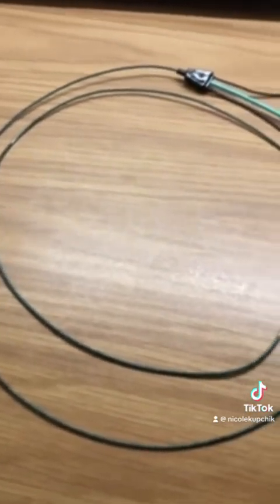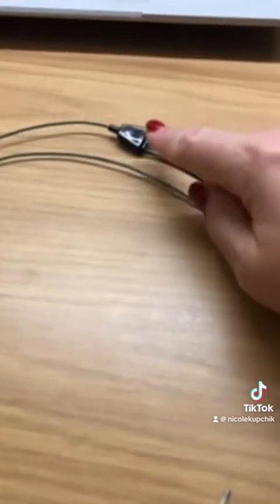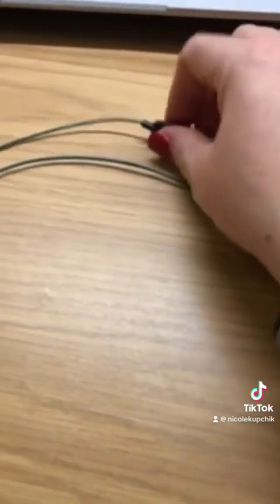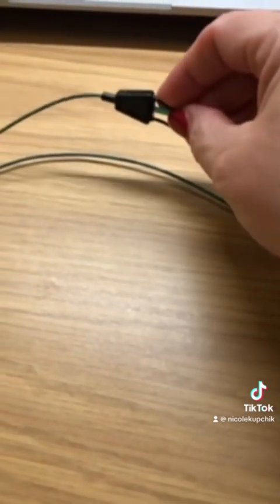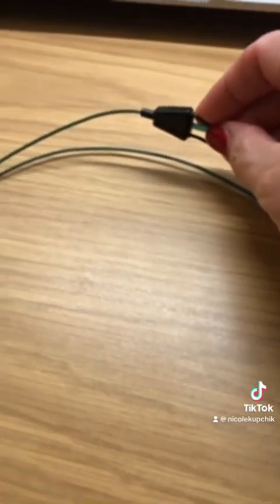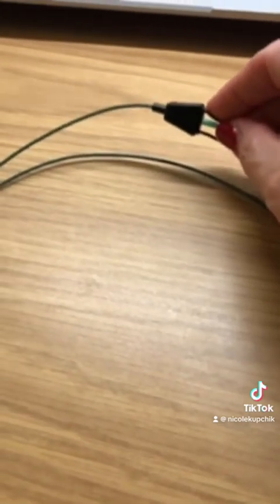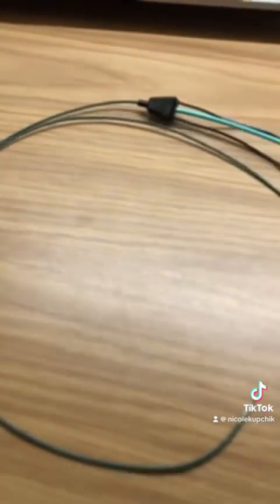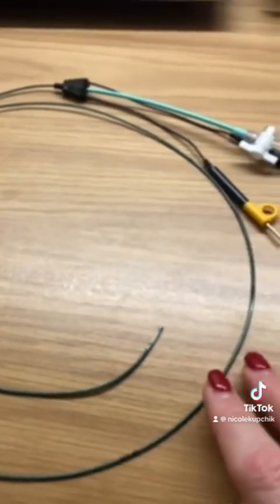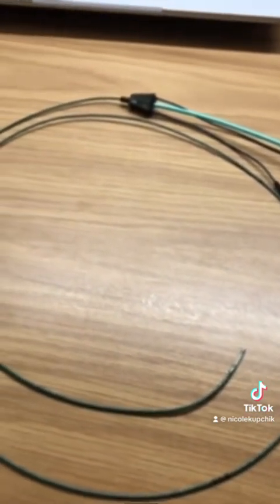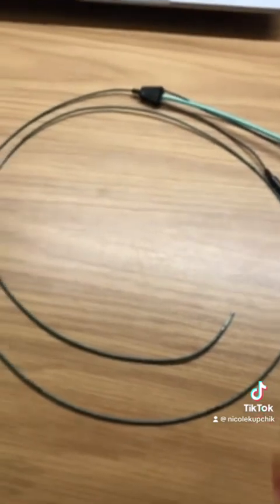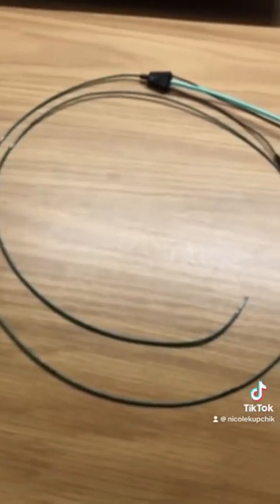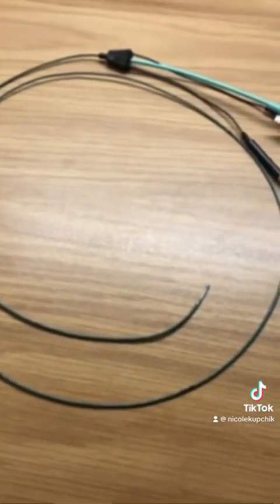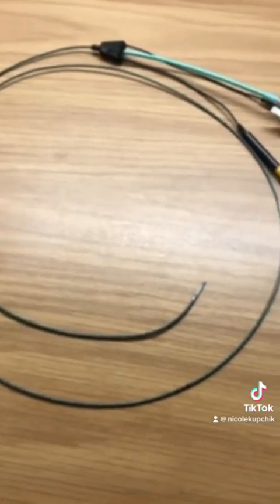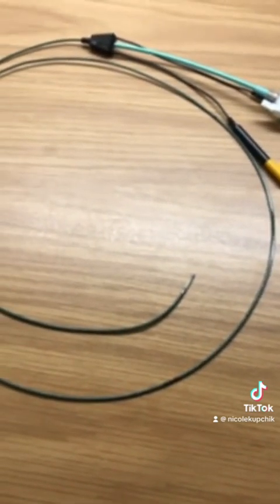And one thing I would just say is just make sure, I usually use this tape. I tape the bejesus out of this to the patient's shoulder just to secure it so that this wire doesn't accidentally get pulled out. And then same thing like with a PA catheter, you want to use what we call a Swan-Ganz sleeve, when we put a PA catheter in, but you want to make sure that the protective sheath goes on before you insert the catheter through the introducer.